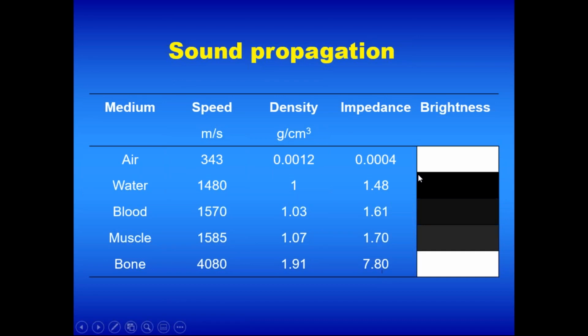The ultrasound machines for medicine are calibrated to a water medium because the tissues have a lot of water in their compositions. So the water represents a black, a completely dark brightness. And blood, as we can see by the difference in the impedance, has a gray color, but it's a dark gray when we compare it with muscle. That is a little more dense, as we see here, and it's a less dark gray compared to the blood and to water. When we look at the brightness of bones in the image, we can see a completely white brightness.